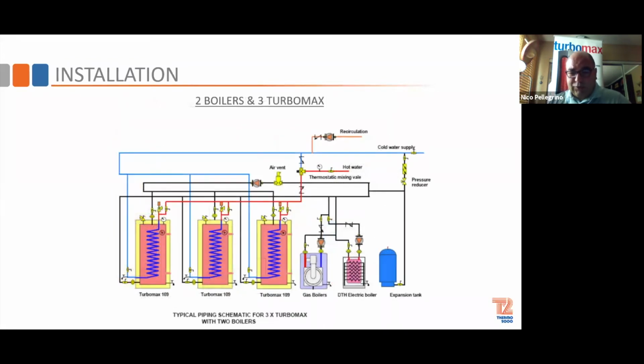So if you're doing multiple tanks, we like first fed, last return. It just gives you an even flow across the Turbomaxes. Here we show it with one pump, but we also have engineers that put a pump on each tank, depending on how they want to call for the heat.